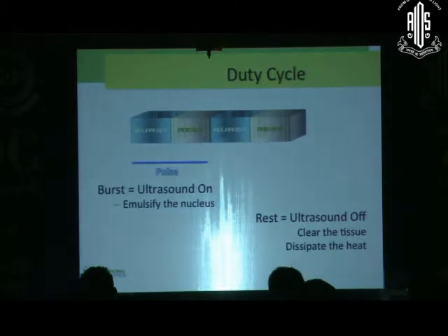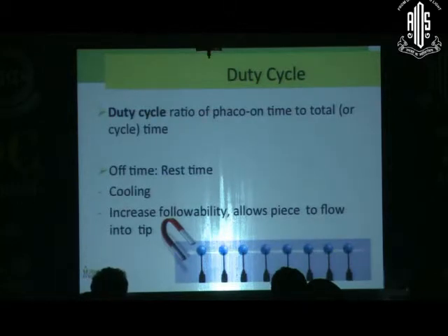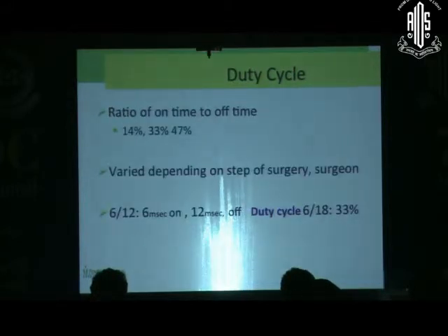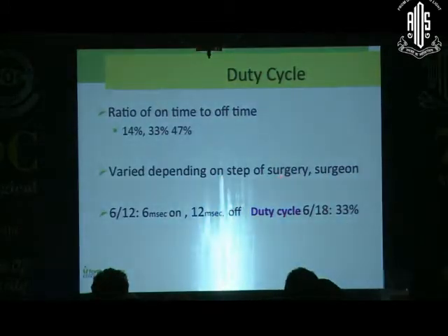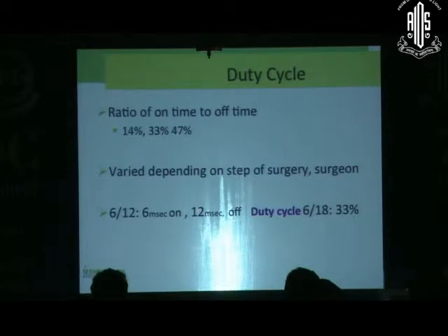So the duty cycle is going to have a burst of phaco, which means there's emulsification, and in the rest, it is ultrasound off, it will clear the tissue and dissipate the heat. So the duty cycle is the ratio of phaco on time to total time, and this is where there is time for cooling in the off time and increased followability, meaning the pieces get drawn into the phaco tip. Now, this ratio can be varied depending on the step of the surgery and the surgeon. For example, in 6/12, it is 6 milliseconds on, 12 milliseconds off, so the duty cycle is 33%.